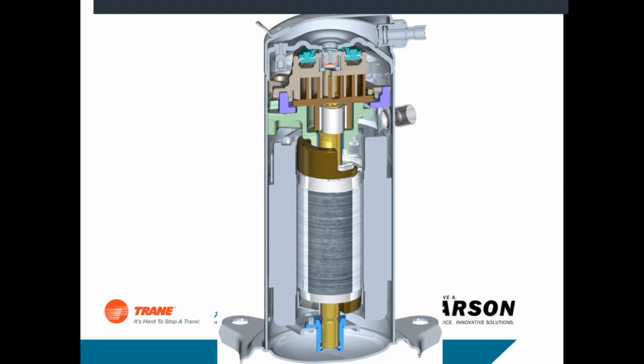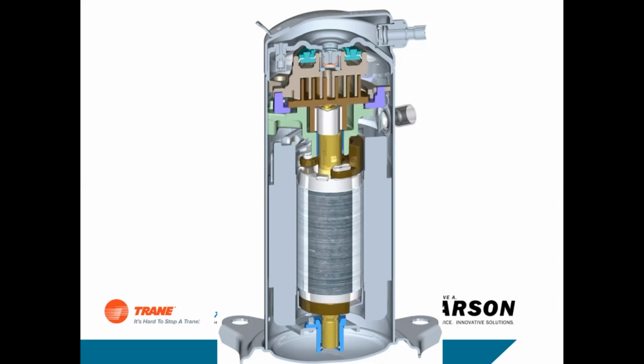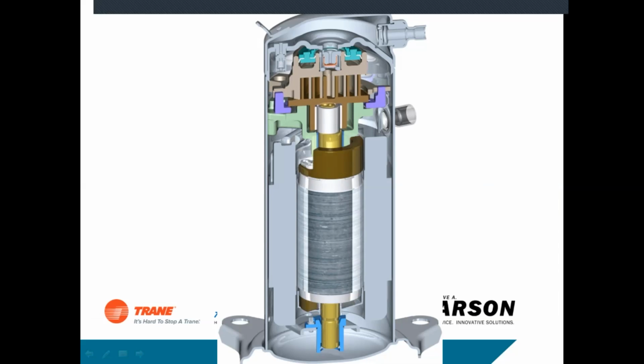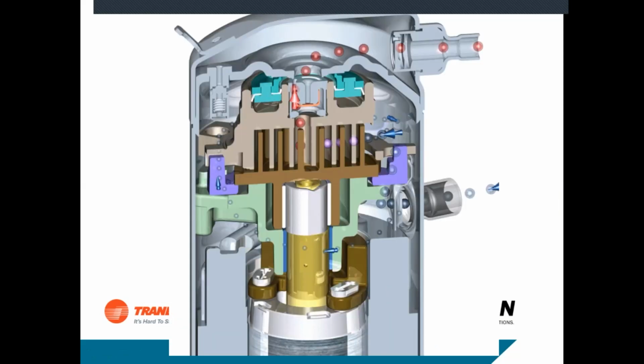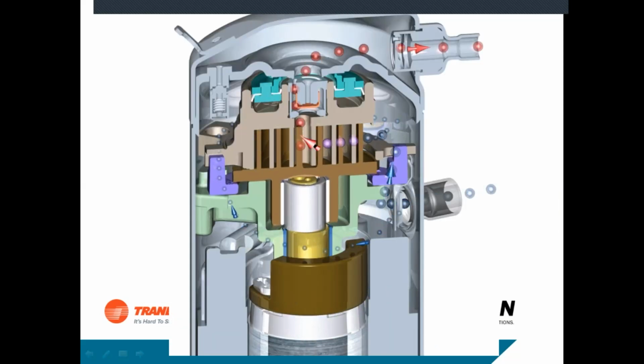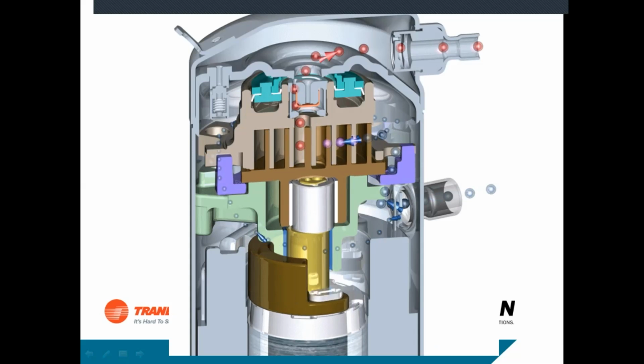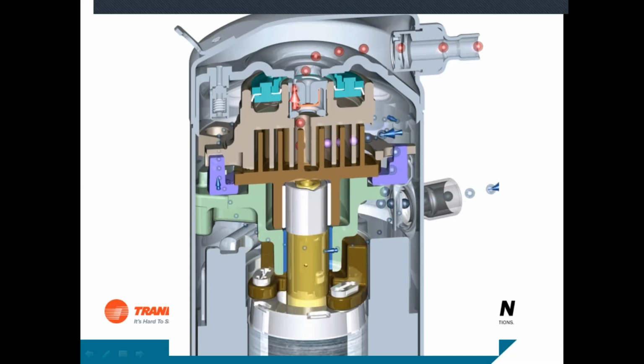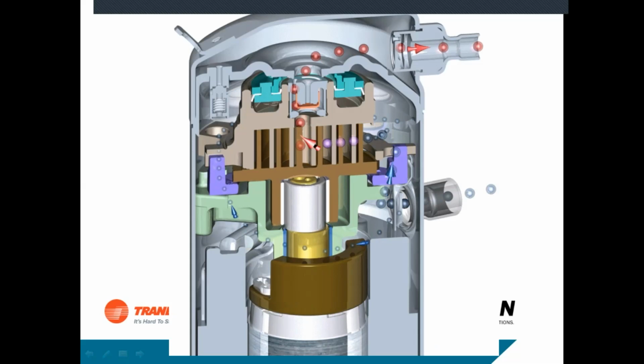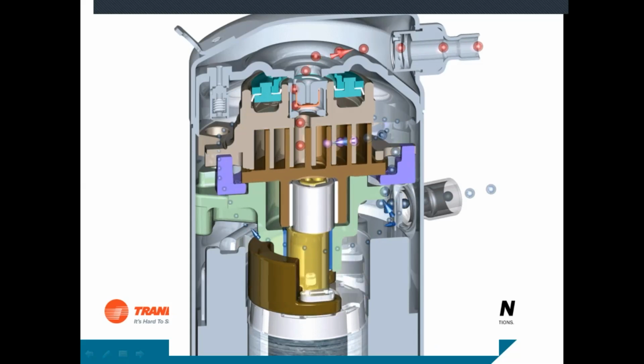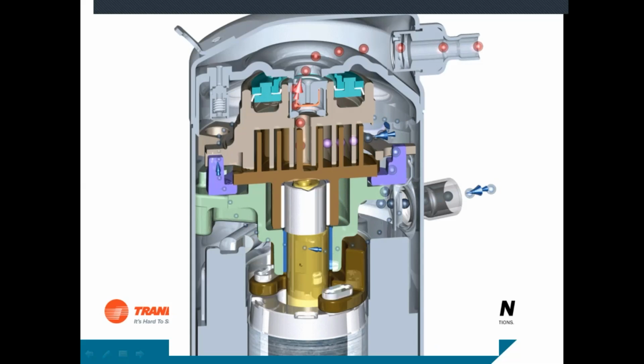All right, now this is an animation of a two-step scroll, the new design. I don't think they're out yet, but they're coming. So it's basically the same compressor. It's got the scroll set in there. It's got the bypass ring on the top for two-step scroll. The difference is this one works off of a three-way valve instead of a solenoid. So it basically does the same thing: takes in gas, runs it through the scrolls, pressurizes it, and sends it into the system.